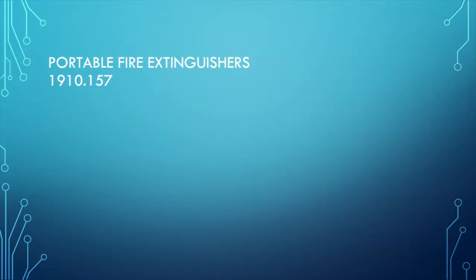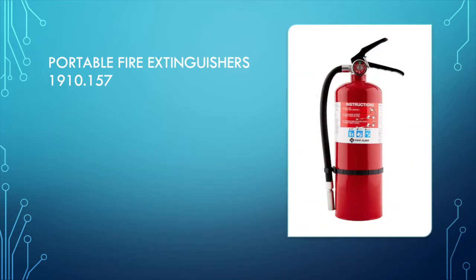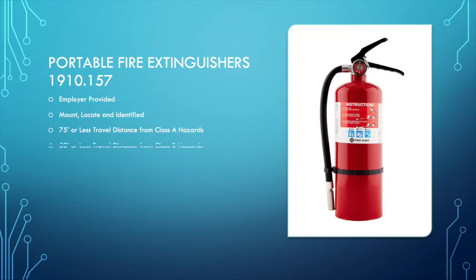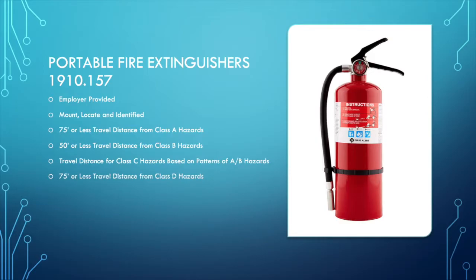Portable fire extinguishers, 1910.157. These are meant to be employer-provided, mounted, located, and easily identified. 75 feet or less distance from a Class A hazard. 50 feet or less distance from a Class B hazard. Travel distance for Class C hazards is based on patterns of A and B hazards. And also 75 feet or less distance traveled from a Class D hazard.